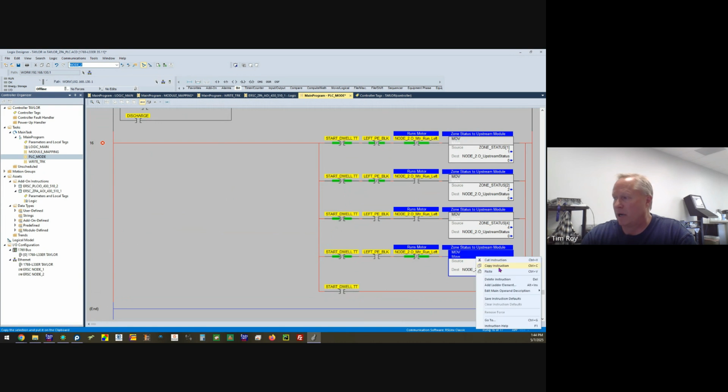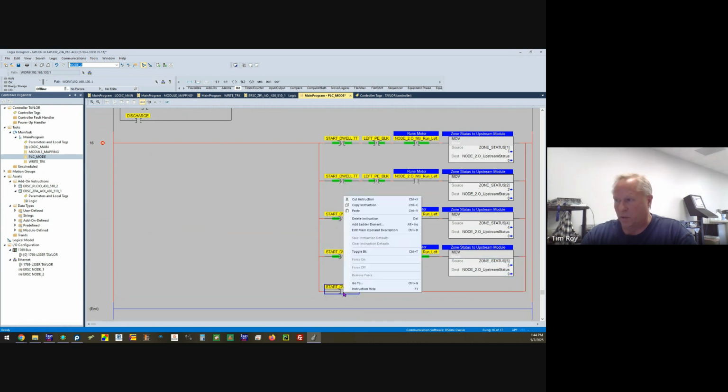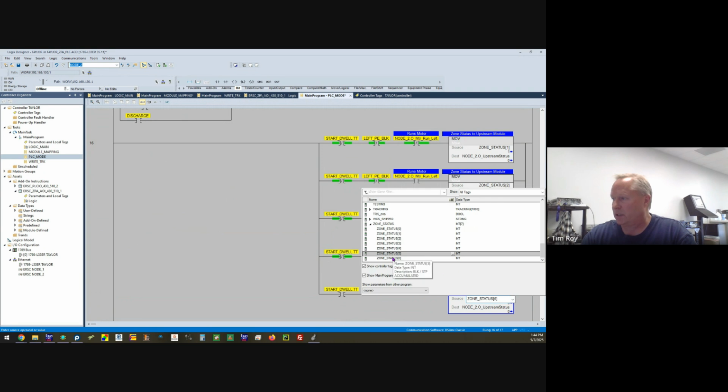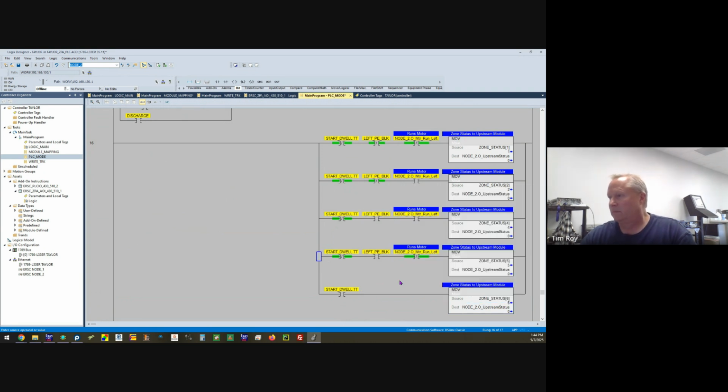If the timer is timing, this is because we're doing our search routine. Well, that's status 6. I'm busy. Gotcha. So we automatically, just like the documentation states, based upon photo eye state and motor state, we're writing the correct zone status. This way the cards will handshake and pass loads just like they're all in ZPA mode. The ZPA card won't know that this is PLC mode because it's talking just like a ZPA card would.